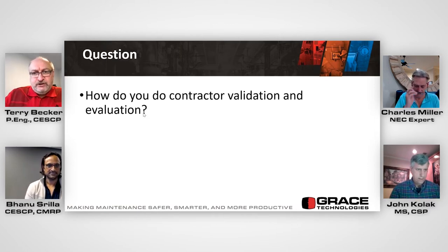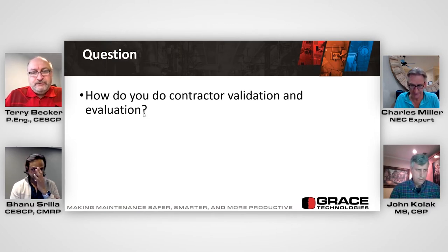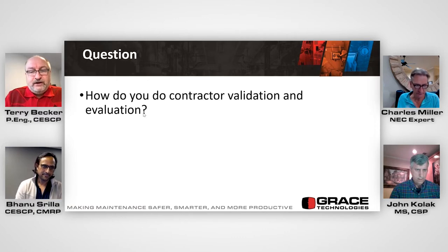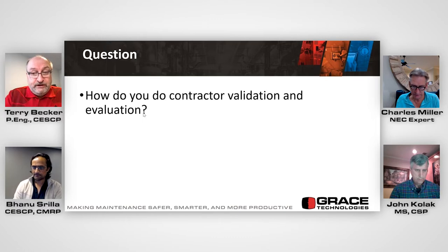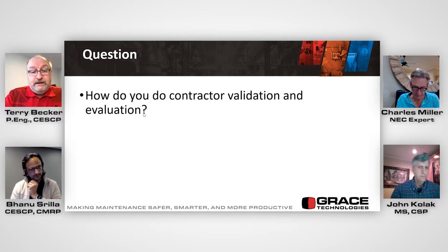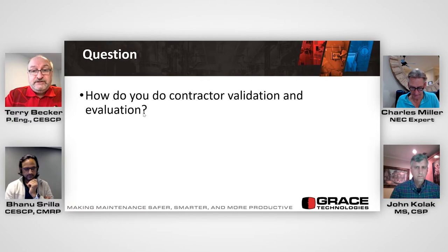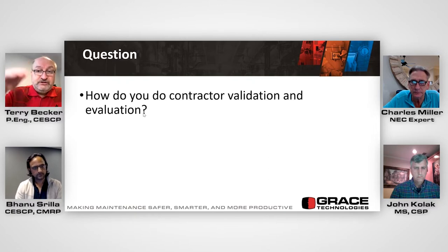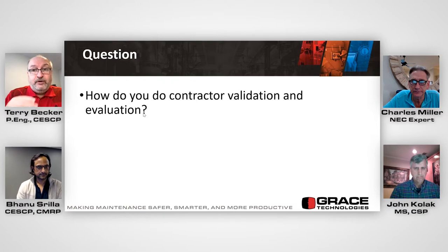I've heard electricians say, how come the contractor's not wearing arc flash and shock PPE? Well, the employer that hires them is the prime. You've got to ask them if they have an electrical safety program and the training records Charlie mentioned, and they should be bringing their own arc flash and shock PPE, not borrowing yours. The same occupational health and safety regulatory oversight applies to the contractor as to the employee, but the company hiring the contractor has additional overarching responsibilities because you're responsible for them on your property.